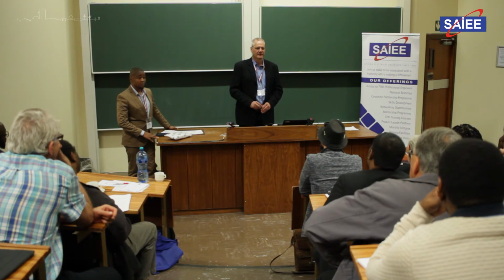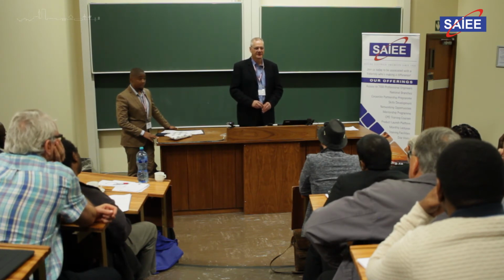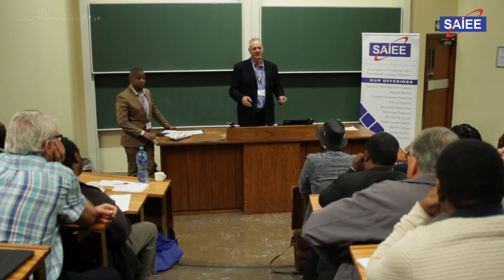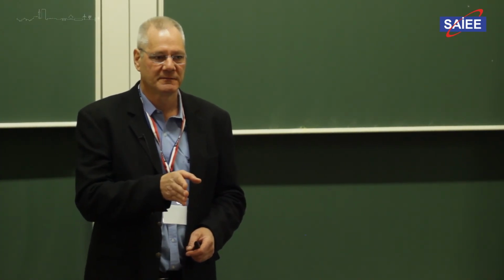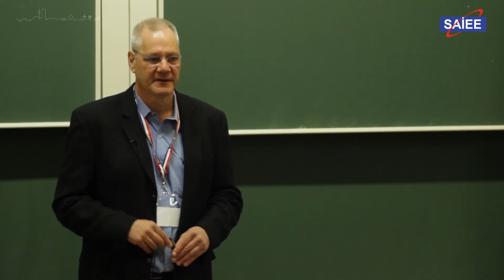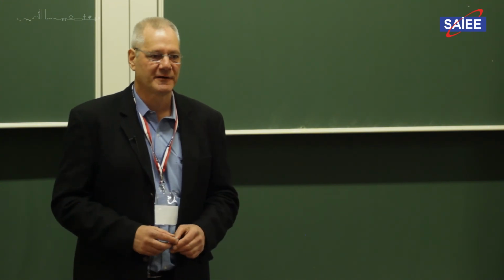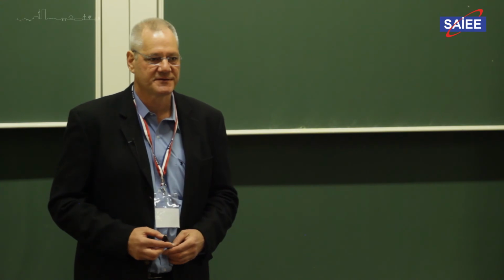Yeah, the way that we define the load classes, you're taking it to domestic specifically, but for domestics, what we're seeing here is that the correlation within is roughly about 0.5. And the correlation between, in other words, different classes of consumers staying in the same place, would be a hang of a lot lower. On average, our way of reasoning with it is that customers of identical class, we give them a correlation of 1, and customers of a different class, between classes, we said that the correlation is 0. That's a practical way of working with it. The reason we make that reasoning is because it saves a hell of a lot of calculations at planning time. Otherwise, you end up with a sparse matrix, and the network traffic is just too high.